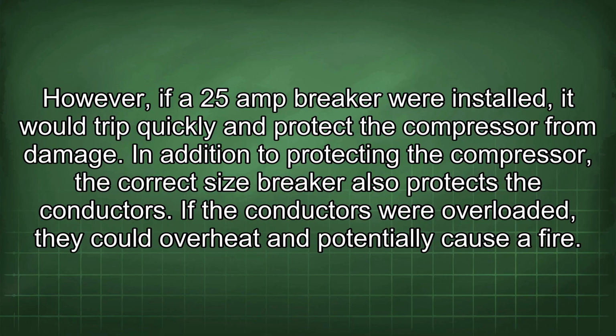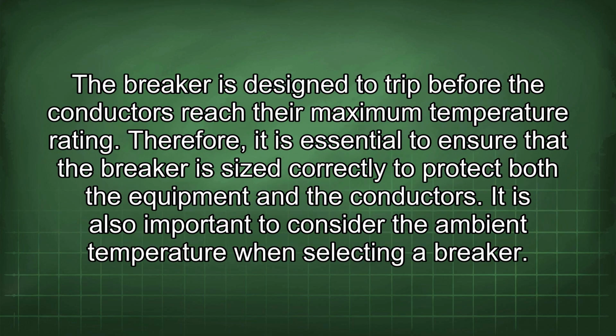If the conductors were overloaded, they could overheat and potentially cause a fire. The breaker is designed to trip before the conductors reach their maximum temperature rating. Therefore, it is essential to ensure that the breaker is sized correctly to protect both the equipment and the conductors.